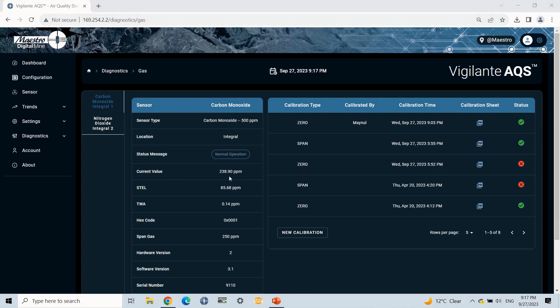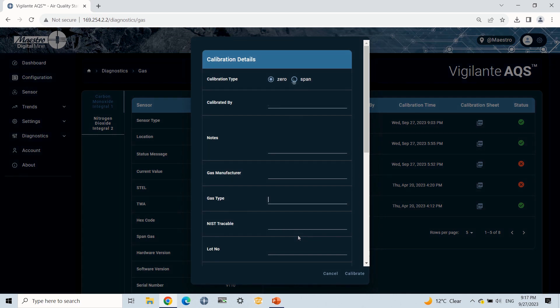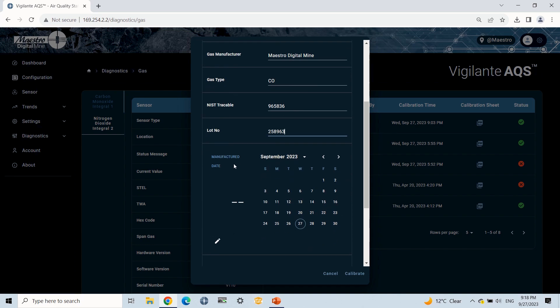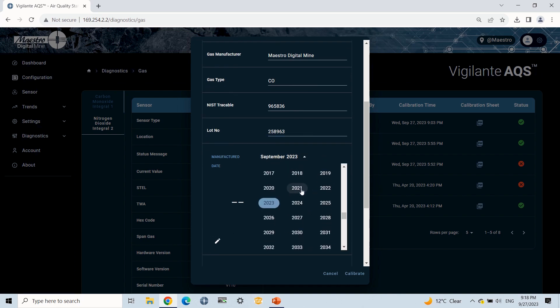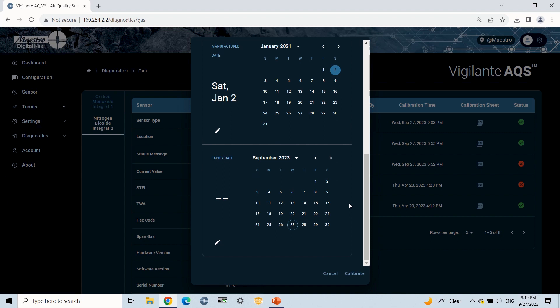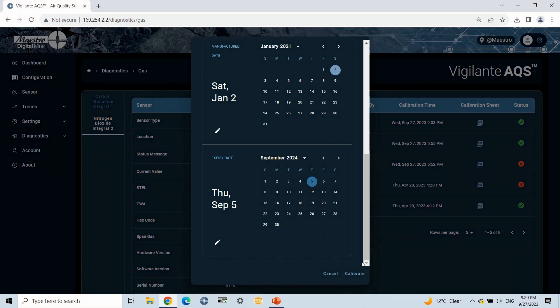Once the real-time value is near to the span value, then I will click on the new calibration button available under the calibration section. This will open a pop-up window and ask for some information such as gas manufacturer, calibrated by, NIST, lot number, expiry date, etc. Now I will write all this information. This record will be used to generate a calibration PDF.